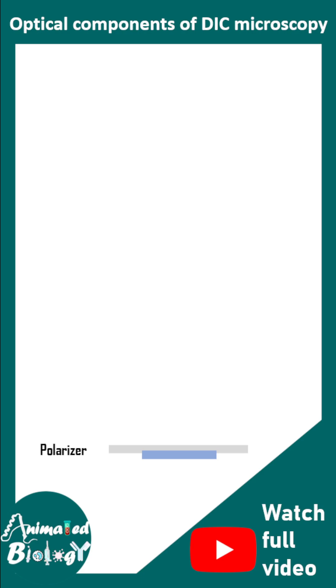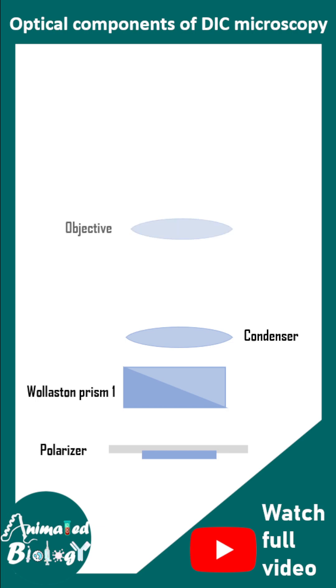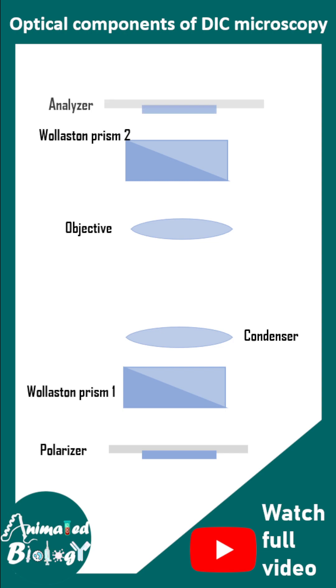The key optical elements in the DIC microscope are: a polarizer, Wollaston prism 1, condenser, objective — which are part of any standard microscope — then Wollaston prism 2 and an analyzer. The analyzer, polarizer, and these two Nomarski prisms are the key components of the DIC microscope. When plane polarized light passes through the Wollaston prism, it is split into two beams: the O-rays and the E-rays.